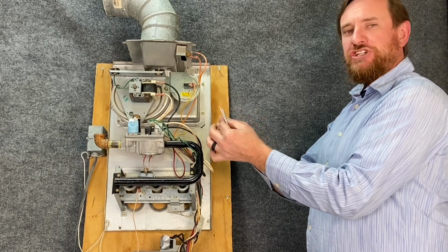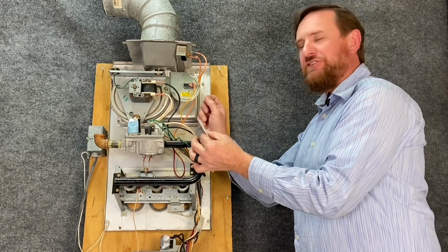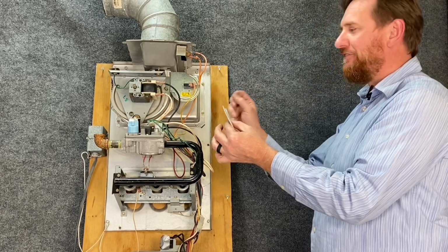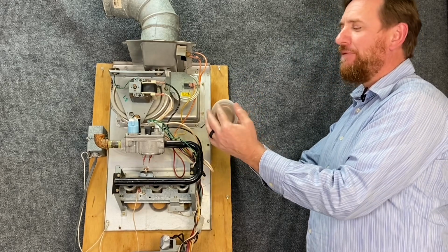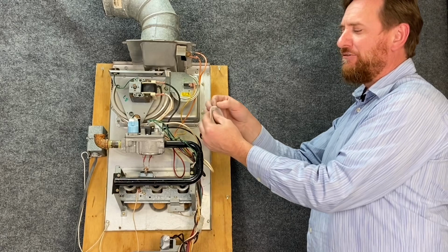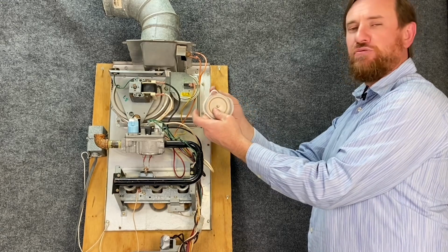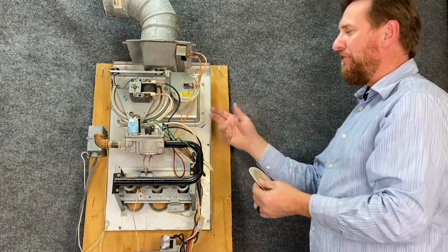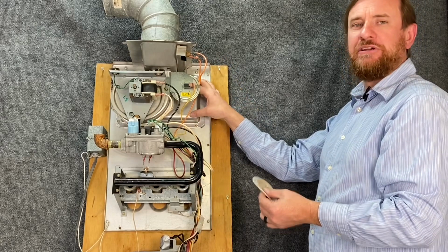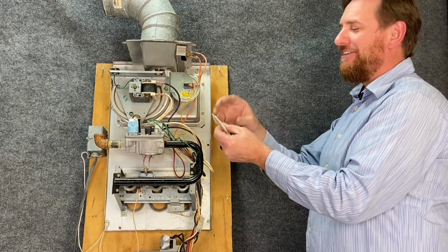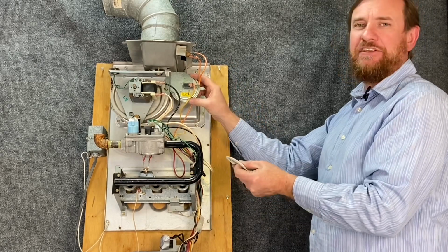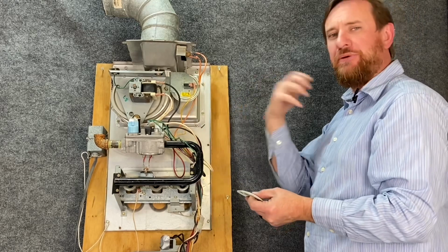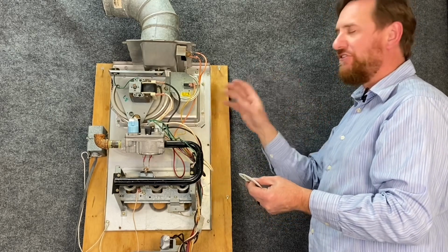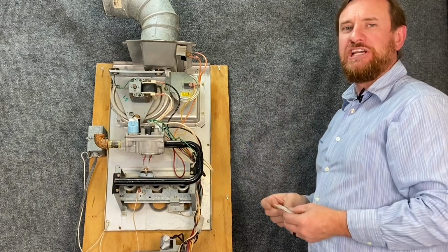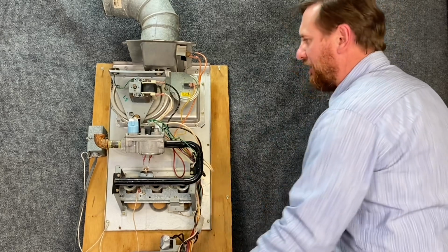It's important that when you're checking this, you don't put your mouth to that tube and suck on it. I've seen people check them like that, but the problem is you pull too hard and it does what happened to this one. It actually rips this diaphragm. The other thing is you have combustion gases, poisonous gases, coming through here, and you don't know what's inside of this switch. So as you're sucking on that, you're pulling all that stuff into your lungs. So it's not a good idea. We want to check it the proper way. So let's talk about checking it the proper way.